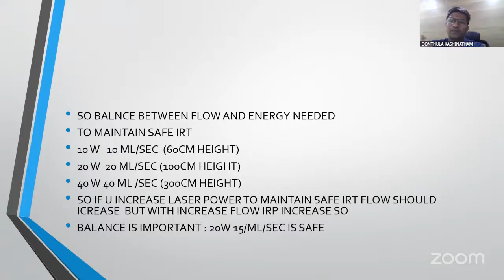One more thing: when you are doing surgery and there is a big stone, there is every tendency to continuously use the laser, which will raise the temperature. Think of coagulation and cutting in monopolar: if you have continuous current, it will cause cutting; if you give interrupted current, it will give a coagulation effect. Similarly, if you give a small pause during laser, the intrarenal temperature will definitely come down. Many studies have shown that if you take a small pause of 3 to 4 seconds, the temperature will drastically come down and the complications will come down.